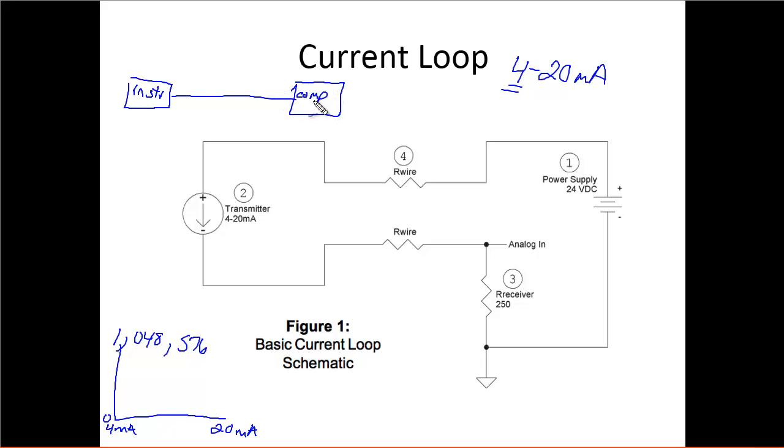And the other thing is, let's see, how this thing works is that actually in the computer or over on this side, it just depends on how these things are working, there's a little computer chip in here that looks like this kind of on the inside and the chip is driving, it knows based on what it's reading here, the chip is driving the appropriate number of milliamps through this signal. So even though the resistance of this wire is going to vary depending on the length of the wire, because there's a smart device inside the system that's monitoring the current and driving the current to what it needs to be, I don't need to worry about the resistance of this line. I can make the lines longer or shorter within a reason, there's going to be a maximum length of the line that you can do. But because there's a smart little chip in here that's driving this, it's going to handle the compensation for it.